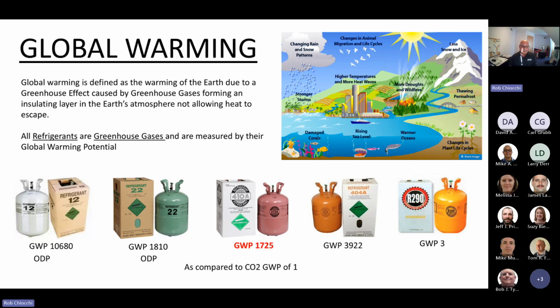I don't typically talk about the politics involved with global warming, but it is a real phenomenon and has to be dealt with. The refrigerants that we've become accustomed to using over the last so many years are deemed to greatly contribute to this global warming phenomenon. All these greenhouse gases are given a global warming potential rating. This rating is all compared to carbon dioxide, which has a global warming potential of 1. Our good friend R410A has a global warming potential of near 1800. So you can see, compared to a natural product like carbon dioxide, R410A is deemed to contribute greatly to global warming, and therefore something has to be done.